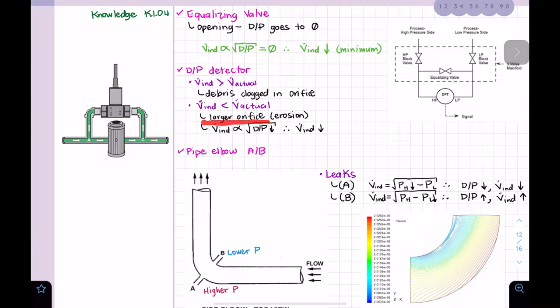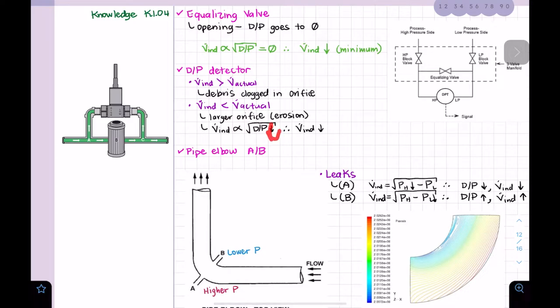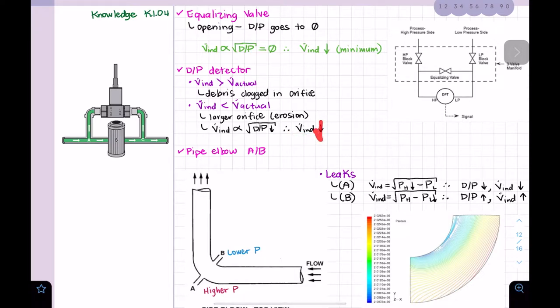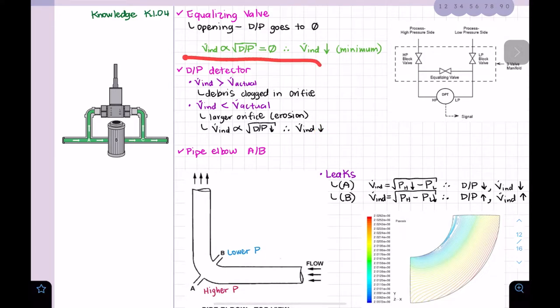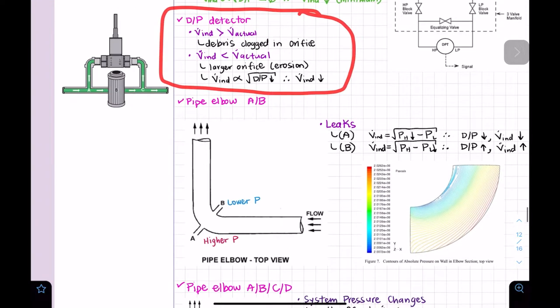A lower-than-actual flow indication could mean the orifice has become larger due to erosion. In flow systems with steam, orifices can erode over time. What we'll see is a reduction in the differential pressure, which reduces the indicated flow rate. That's all we need to know in this section for GFES.